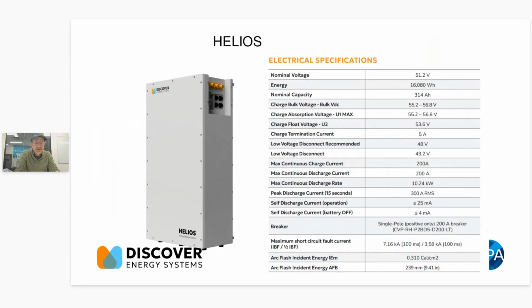You see here we've got the specs that I was talking about before. So we've got the capacity of 314 amp hours, and then the maximum discharge rate is 300 amps RMS, which gives you what your surge is going to be. So that's sort of another point I'd like to just hammer in a little bit about your system design, is that you shouldn't really be designing things to be right on the edge. You shouldn't really be expecting to use that 300 amps surge, unless it's for some sort of emergency scenario or something like that. You should have headroom for these things. You don't want to be operating anything right on the edge, because you're just inviting issues. And usually in those scenarios, the capacity of the battery wouldn't be well matched to a load like that anyway. So you're not normally going to get into that type of situation.